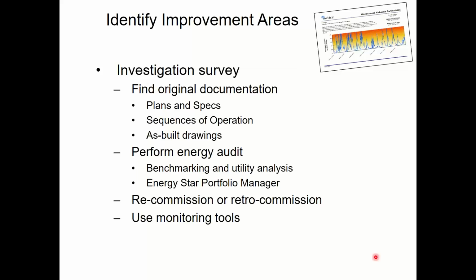And that may be fine, and maybe I want to pay to do that. Or maybe just twice a year when I do my maintenance on my air handling systems and my coil cleaning and whatever, maybe those times I want to just check static pressure and note it in the log. And then if it's changing over time, I can be like, why is it not what it used to be 3 years ago, kind of thing. So it can be kind of an instantaneous snapshot, or it can be a continuous monitoring type tool. I gave pressure as an example, but you can do the same things with temperatures and humidities and things like that.